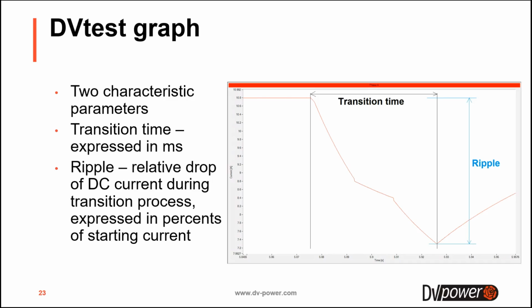It is typically 30, 40, 50 milliseconds, can be 60, but generally if it is higher than that, then that represents a problem, probably in the mechanism of the tap changer. The second parameter that we also monitor is the so-called ripple. It is a relative drop of DC current during the process, and we express it in percents of starting current. The ripple is represented here with the vertical blue lines.